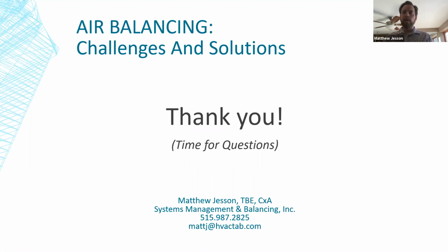And in round ducts, there's a requirement that I believe is 16 readings. Now I'm going to lie to you somehow. Round duct traverses are a little different because you have to space your readings differently, because you're basically forming concentric rings of equal area. So if anybody has a particular question on that, feel free to reach out to me and I can get you the exact data out of our manuals. I've got no problem doing that. Quoting it off the top of my head is going to get me in trouble, I think.